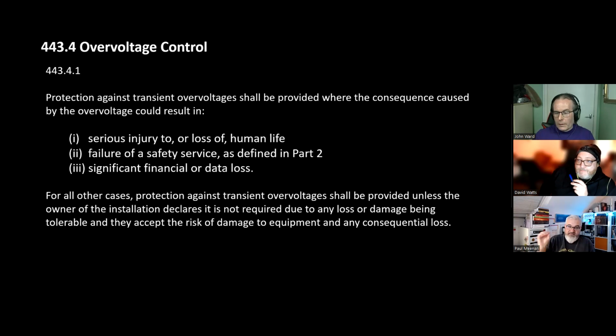For all other cases, protection against transient overvoltage shall be provided. So if it's not in M3, you're still providing it, unless the owner says no. Okay, that's going to be an interesting document to write. So I think this is far easier. That thing with the owner stating it, basically, I'd steer well away from doing that, particularly on domestic.